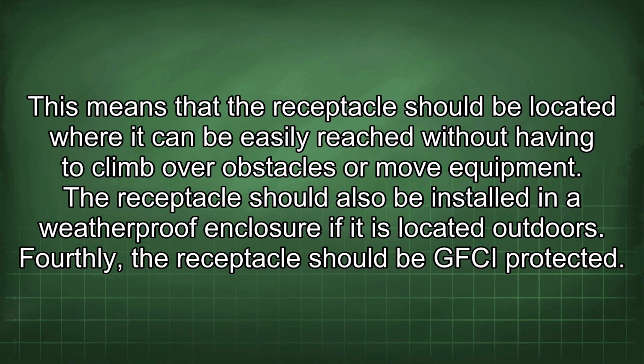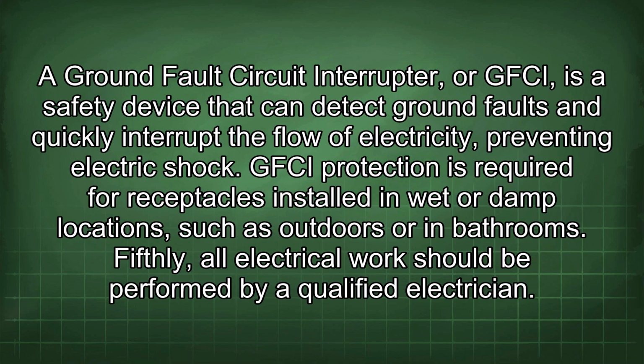This means that the receptacle should be located where it can be easily reached without having to climb over obstacles or move equipment. The receptacle should also be installed in a weatherproof enclosure if it is located outdoors. Fourthly, the receptacle should be GFCI protected. A ground fault circuit interrupter, or GFCI, is a safety device that can detect ground faults and quickly interrupt the flow of electricity, preventing electric shock. GFCI protection is required for receptacles installed in wet or damp locations such as outdoors or in bathrooms.